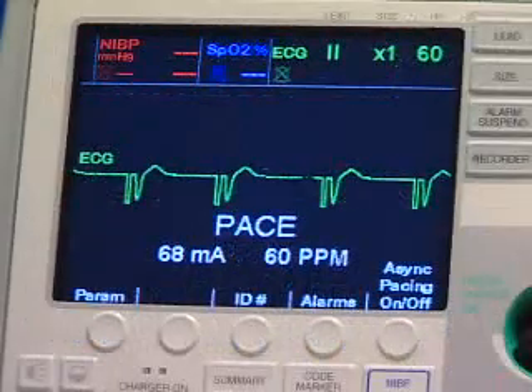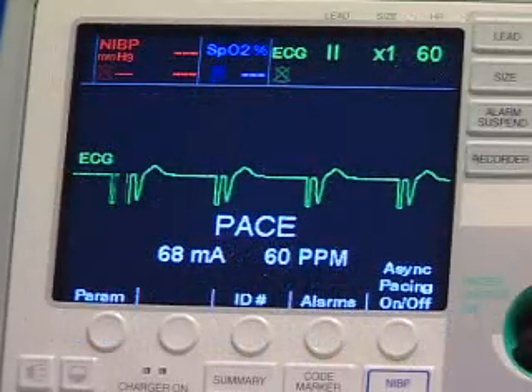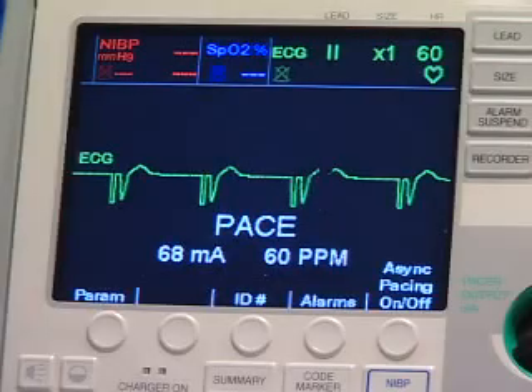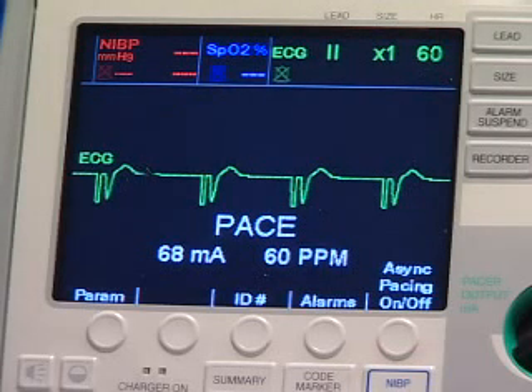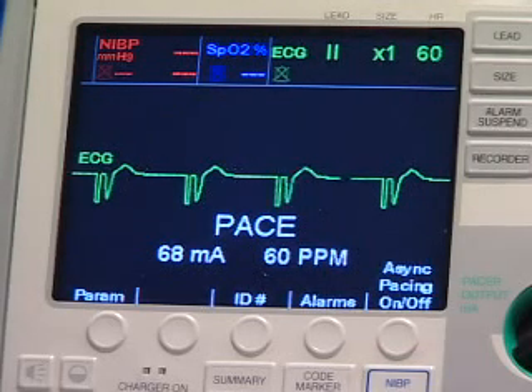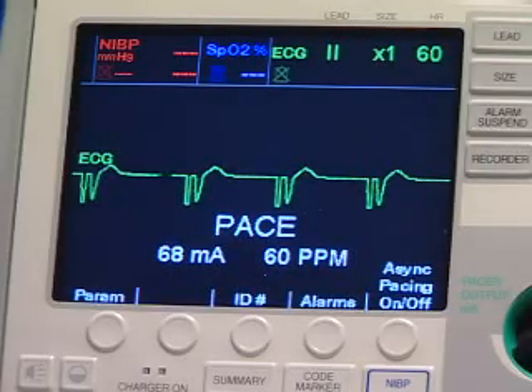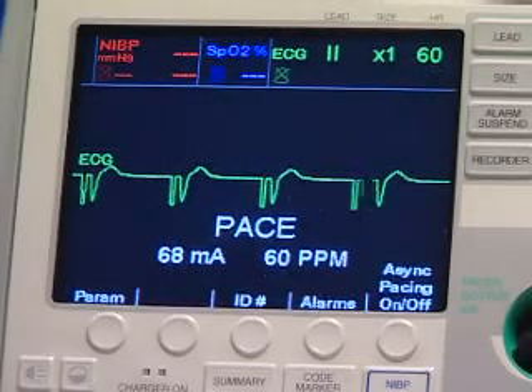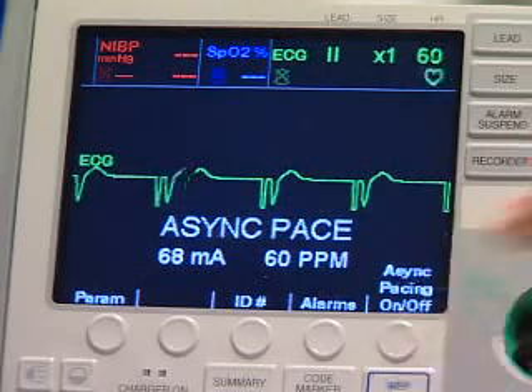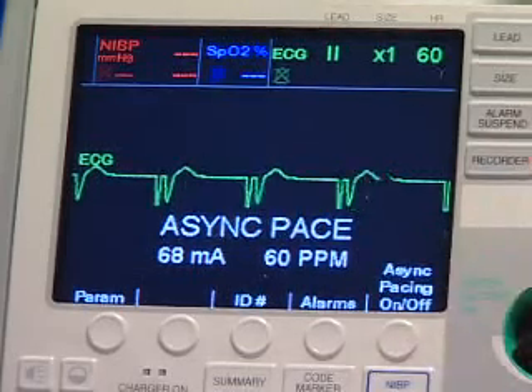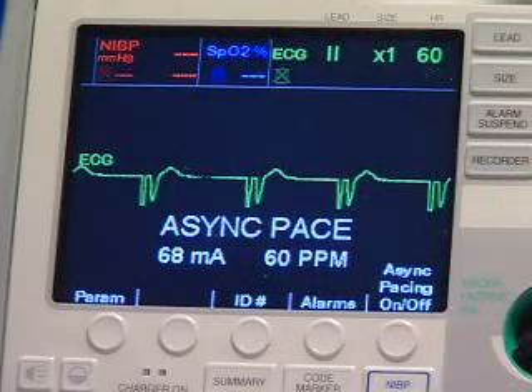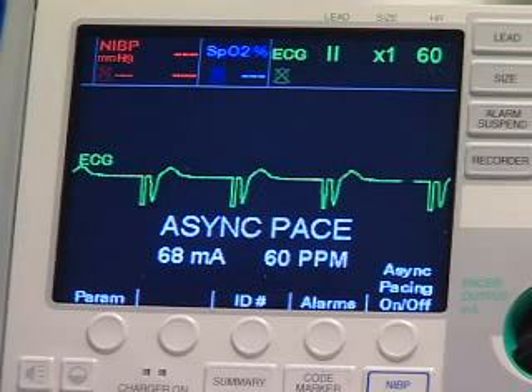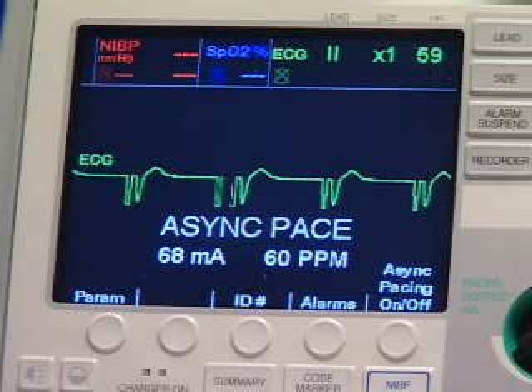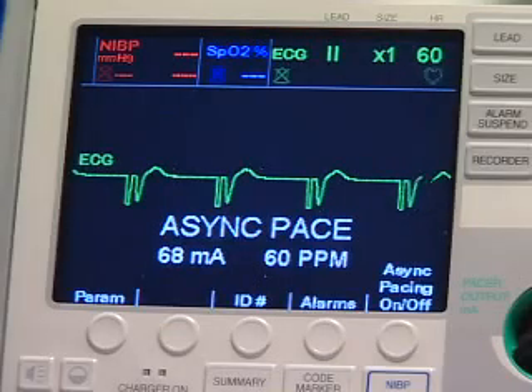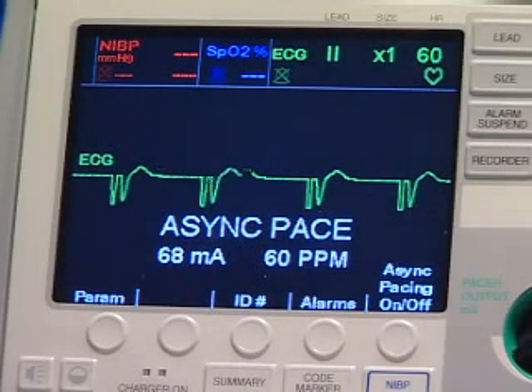If ECG electrodes are not available, or there is something that interferes with the surface ECG, you can operate the pacemaker asynchronously. You should only do this in emergency situations when there are no other alternatives. Press the Async Pacing On-Off key. The E-Series display will show the Async Pace message. This is also printed on the strip chart when activated by the Recorder button. To return to demand pacing, press the Async Pacing On-Off key again, and the display returns to pace.